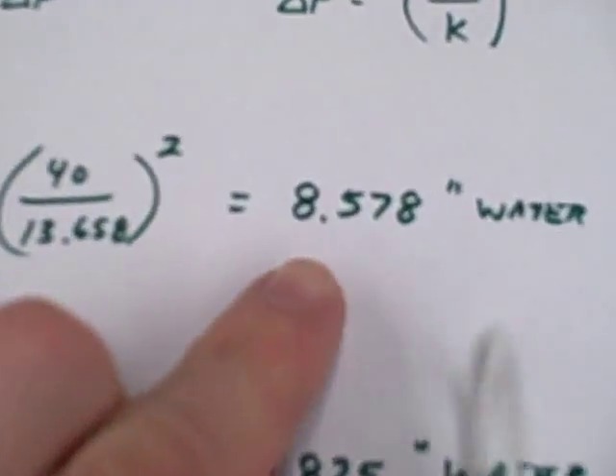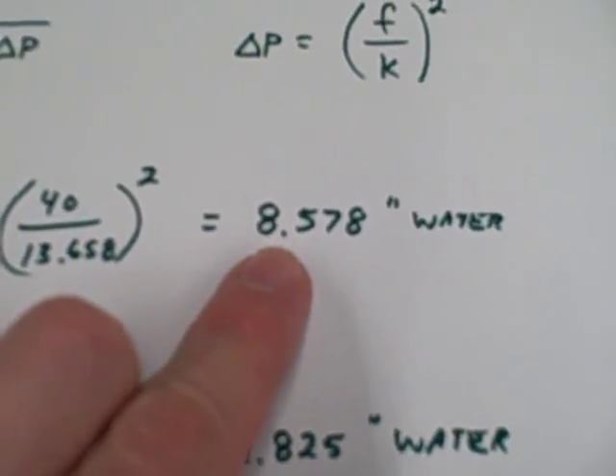Notice that we calculated 8.578, so we're awfully close to our predicted measurement. 8.578 inches of water calculated and about 8.6 inches of water here.